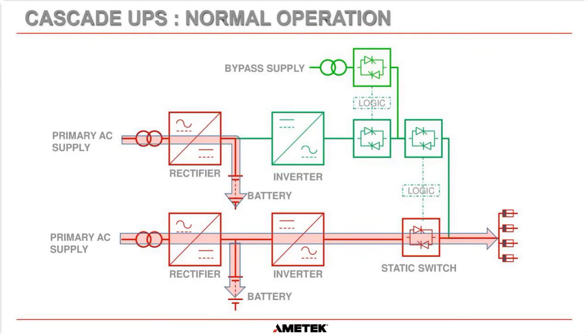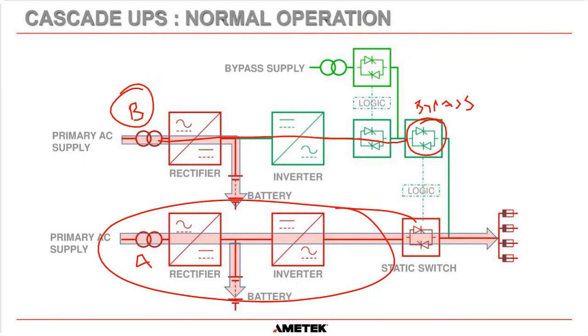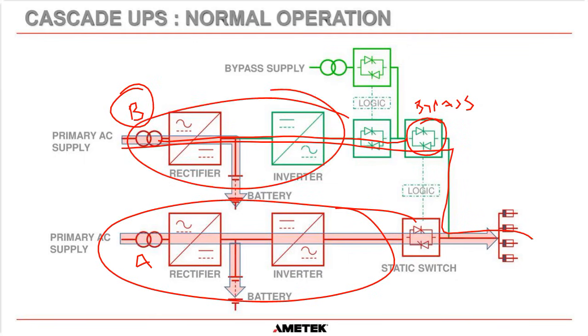And then this topology is called a Cascade UPS. There's a lot of confusion surrounding a Cascade UPS, but the easiest way to remember it is if you have UPS-A here and UPS-B here, UPS-B is feeding the bypass supply. So this is the bypass static switch for UPS-A. Really what we're doing is putting a UPS onto the bypass supply. Therefore, if something goes wrong with UPS-A, when we transfer to bypass, we still have a UPS backing it up. We still have battery backup. We still have clean power going to your load circuits. So it's actually a very good arrangement.